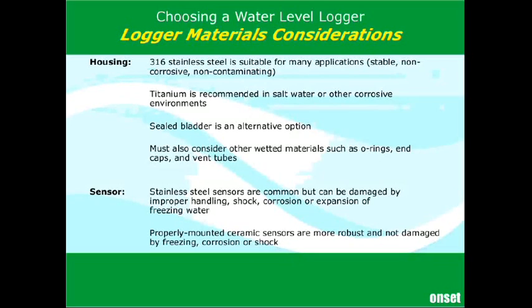The stainless steel pressure transducer is a little more susceptible in that its diaphragm is a thin foil of stainless steel that's easily permanently deformed, whereas the ceramic is more of a hard plate, although it can also be cracked. As far as temperature extremes go, typically the loggers can't withstand very high temperatures because they're limited by their battery performance, and batteries can't deal with too much temperature. And most of the loggers are temperature calibrated. As I discussed, in our case, we pressure cycle and temperature cycle them and calibrate them over a range of 0 to 40 C. So that's pretty much the temperature range it's expecting to see in standard water applications. That covers logger material. At this point, I'm going to hand it back over to Nick.